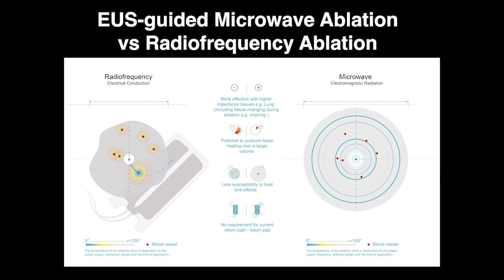Microwave ablation is based on frictional heating produced through the oscillation of dipole molecules, inducing a controlled temperature rise up to 90 degrees Celsius. This novel technique provides a homogeneous and consistent energy deployment without eliciting any damage to surrounding structures. In contrast, radiofrequency ablation is based on a high-frequency alternating current of 450 to 500 kHz, reaching temperatures beyond 100 degrees Celsius. A theoretical benefit of microwave ablation is that it is less susceptible to heat sinks.